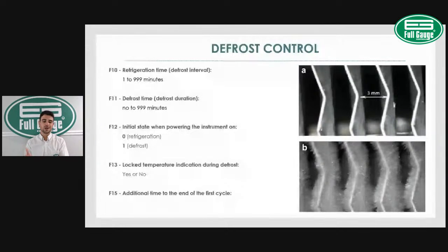So again, the functions we would be changing: F02, set point, and F06, differential. Those are my cut-in and cut-out temperatures. And F10 and F11 for the defrost interval and defrost duration. For most medium temp applications, only those 4 settings have to be changed. But now we're going to be looking at other parameters that can be changed to increase the efficiency of the refrigeration system.